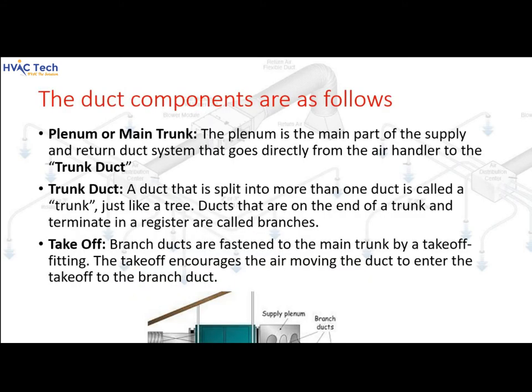The duct components are as follows: the plenum or main trunk is the main part of the supply and return duct system that goes directly from the air handler to the trunk duct. A trunk duct is one that is split into more than one duct — just like a tree. Ducts that are on the end of a trunk and terminate in a register are called branches. Branch ducts are fastened to the main trunk by a takeoff fitting, which encourages the moving air to enter the branch duct.